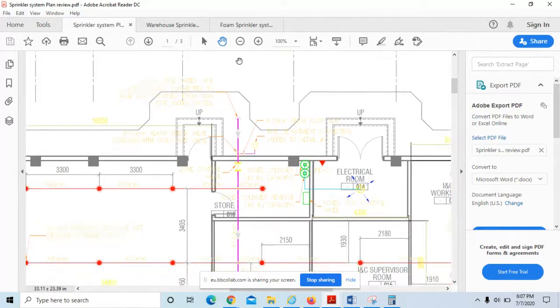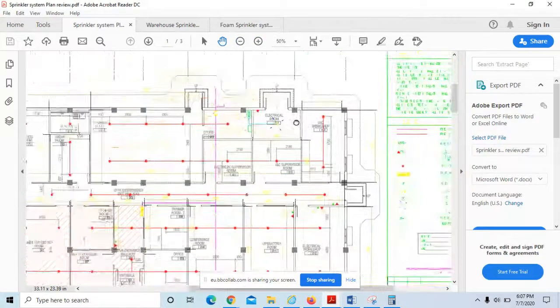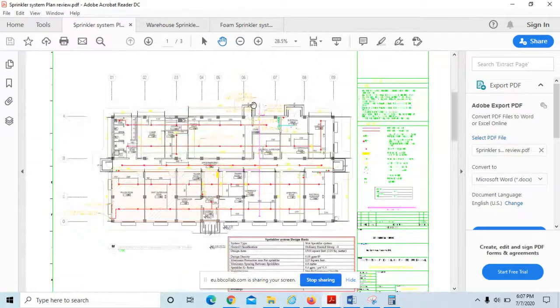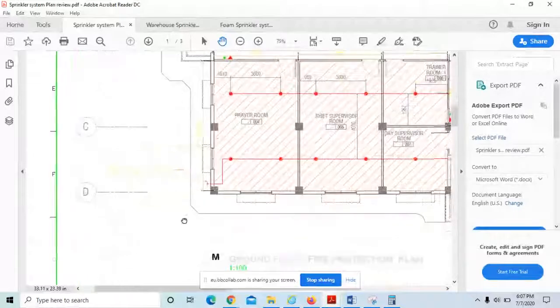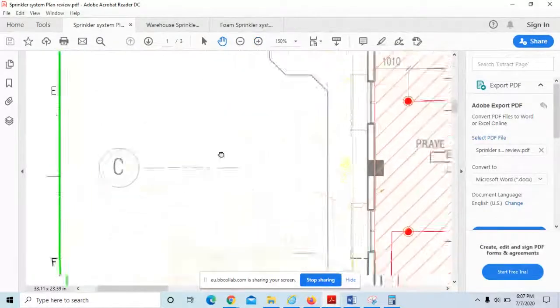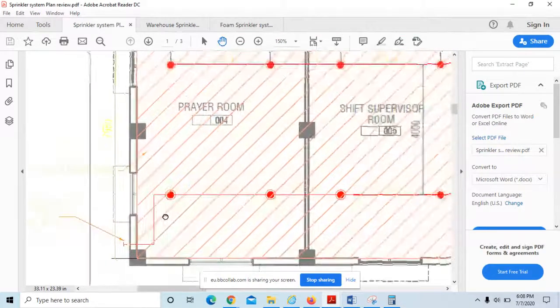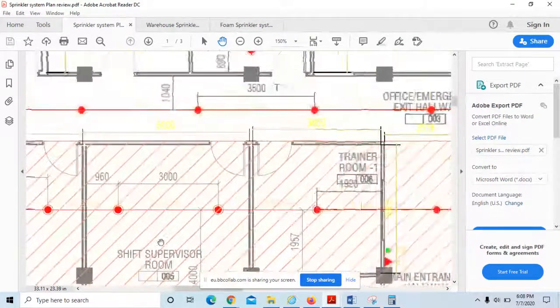So what's the problem? No, there is no problem. I'm just showing how the drawing is coming. There is no problem in that. The purple one is the riser, and the remaining one in red is the sprinkler piping, right? At the most remote location, they have provided one 25 mm test and drain connection as per the design requirement, right?